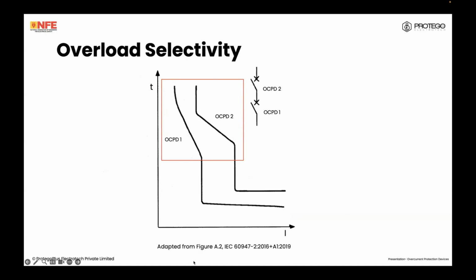If there is separation, then for a certain overcurrent, this will trip in this much time, and this will not trip. First, over here, this will trip in this much time, and this will take a lot more time to trip. So the times are far enough for the upstream OCPD to not disconnect. In the case of fault currents, you see, they are too close, because it's a logarithmic graph, remember. These values are insanely close to each other. There is not enough separation. Therefore, you have to do a depth study.